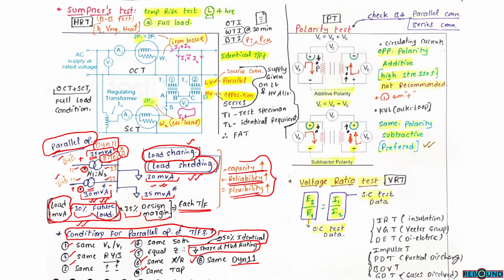We can have different ratings of transformers in parallel also. In that case, the load sharing depends upon the rating of the transformer, percentage impedance and X by R ratio.